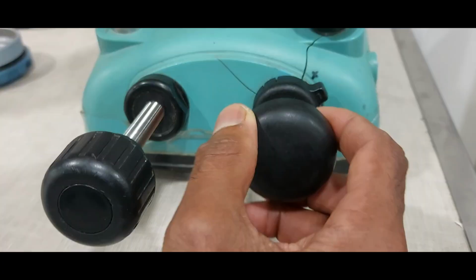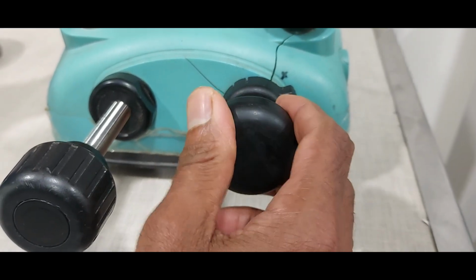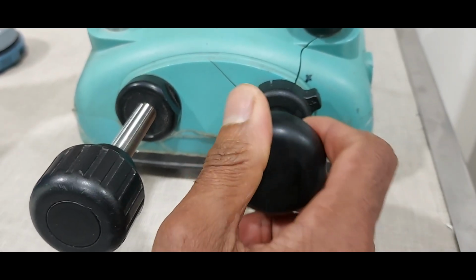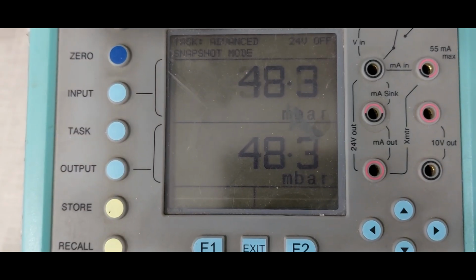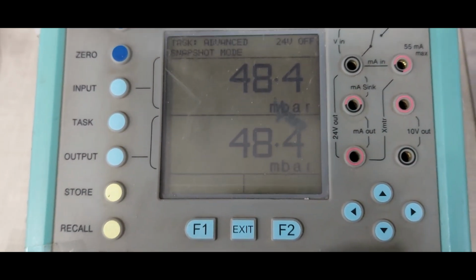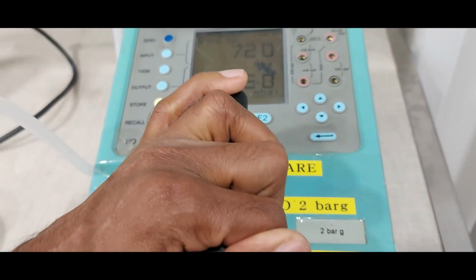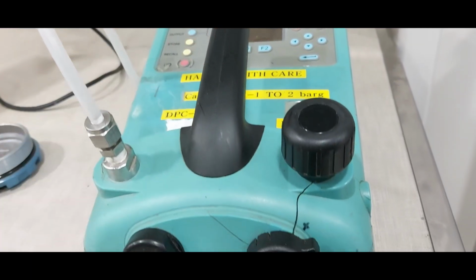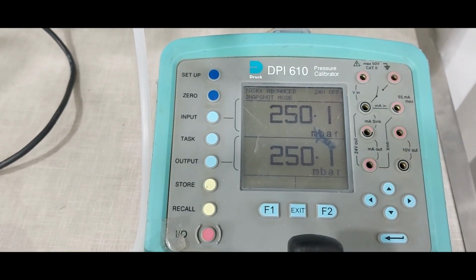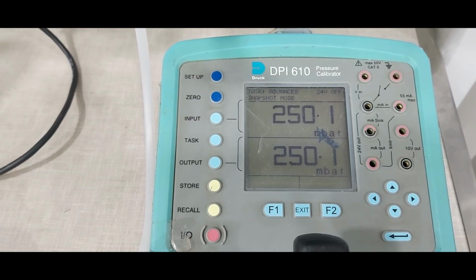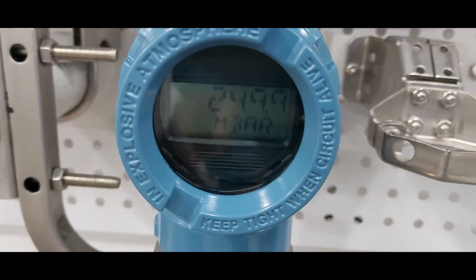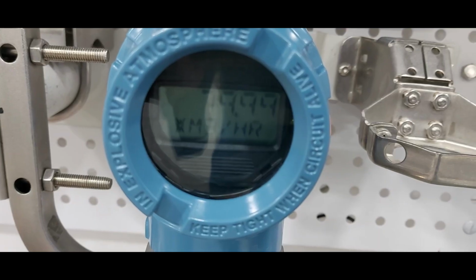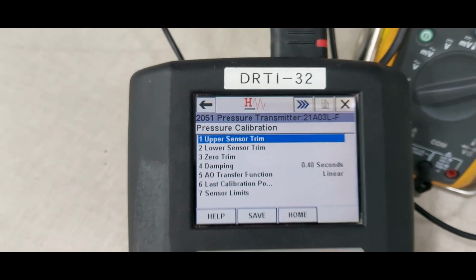Next close the valve in the pressure calibrator unit and apply the pressure to 250 millibar. Slowly apply. Now pressure has reached 250 millibar. The transmitter display is showing 249.9 millibar. Next we are doing the pressure sensor trim.